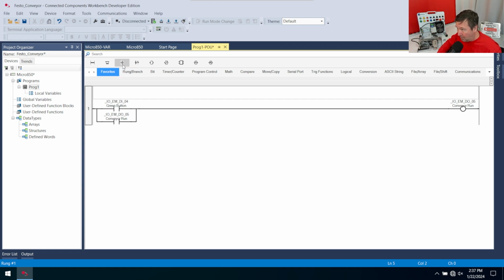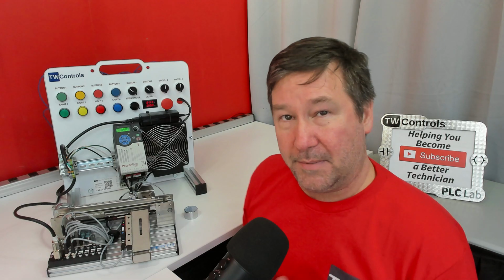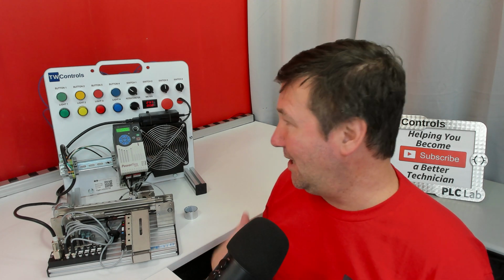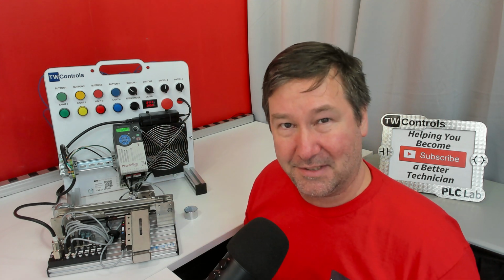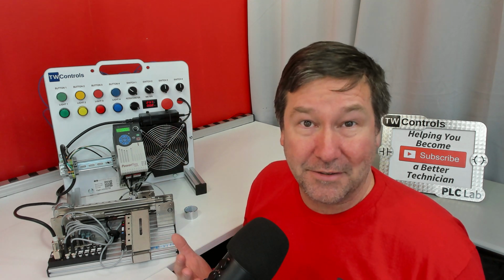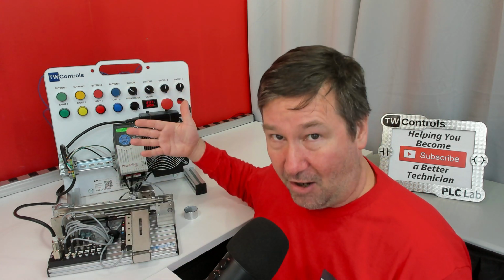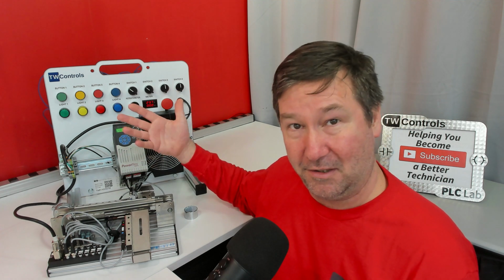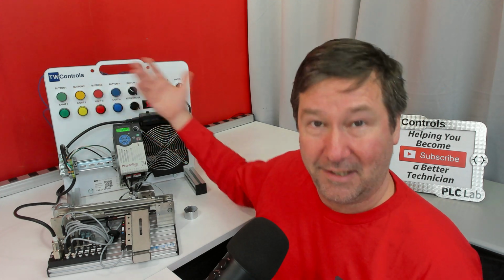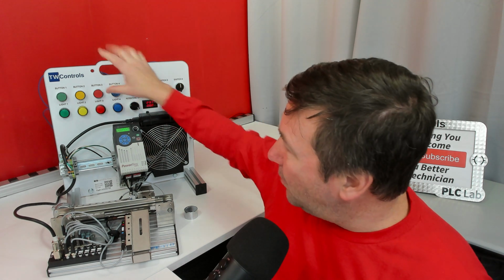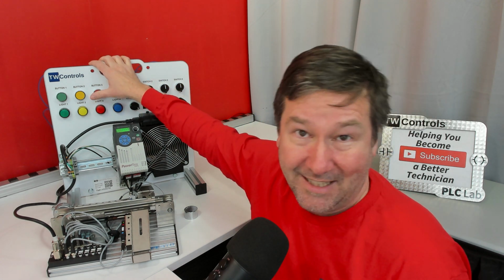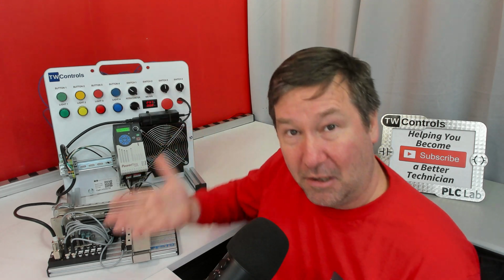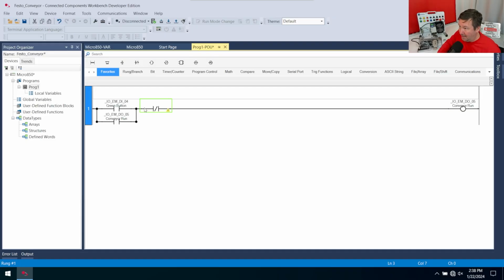Now, let's talk about how we would figure this out. Because when you're thinking about those instructions as normally open and normally closed, and you're thinking about these as normally open and normally closed, it can get really confusing. And this is why I use the go look for a 1 and go look for a 0. So if the input is off, it will have a 0 in it. We use the go look for a 0. If the input is on, it'll have a 1 in it. We'll go look for a 1. So when I'm not pressing the red button, it has a 0 in it. So we want to go look for a 0. Bring that down. And we're going to put the red button in.